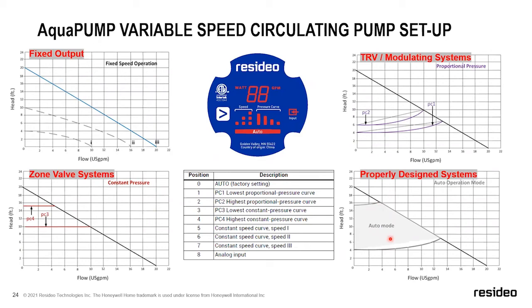If you do run into a couple other modes, or you want to tweak this a little bit, we have 2 different pressure curve settings. So that's going to fall right in these different modes. I'm going to start with PC1 and work my way backwards. So PC1 is here, PC2 is right here. Your PC1 is a proportional pressure curve. What that means is it is going to mimic a system curve with a system like TRVs, which is an acronym for thermostatic radiator valves, or modulating valves, like modulating fan coils, etc.